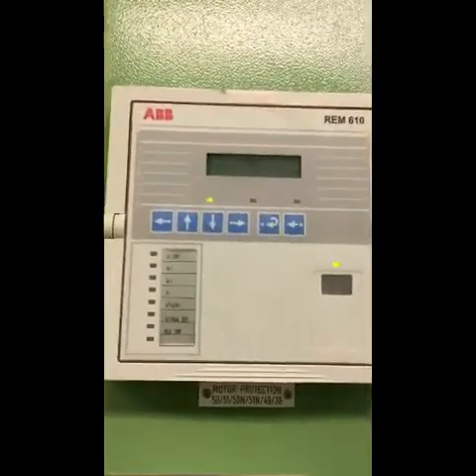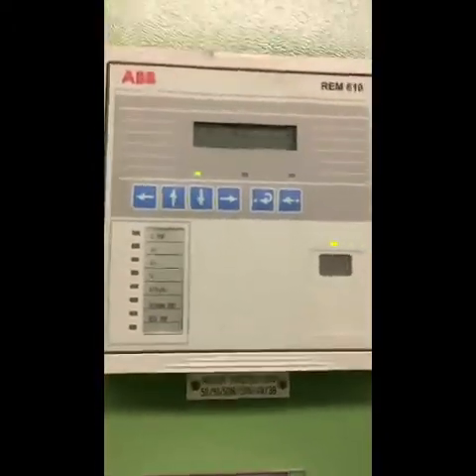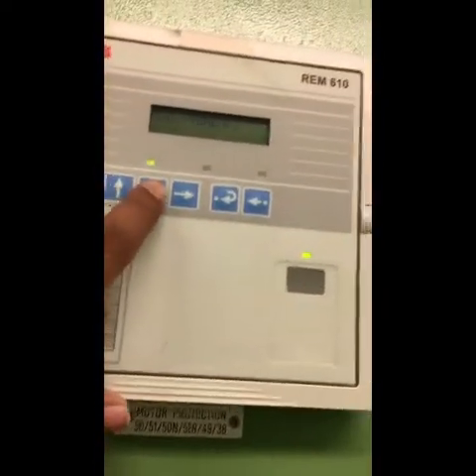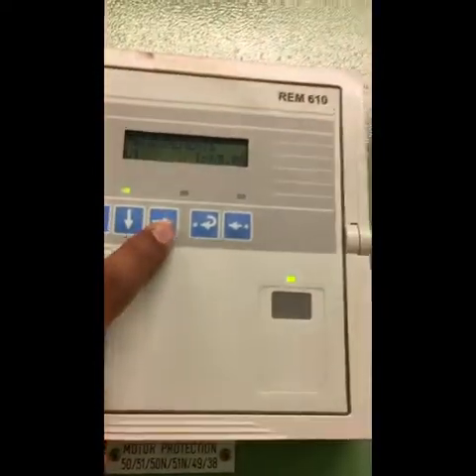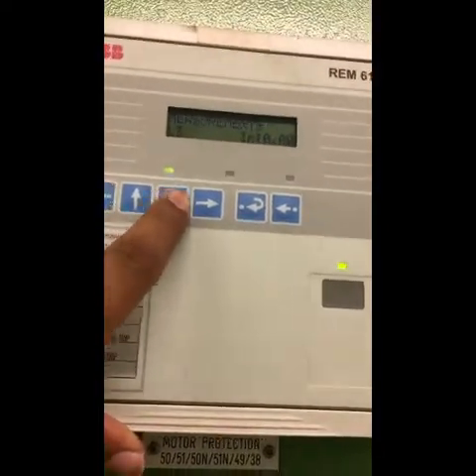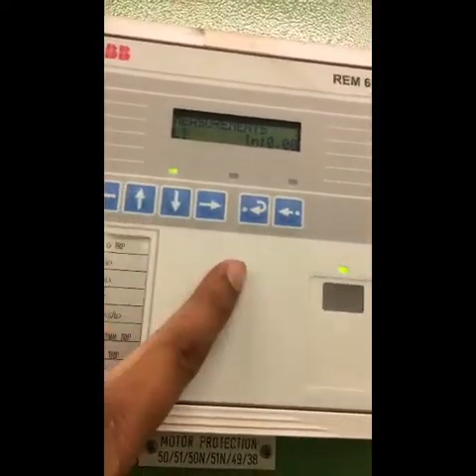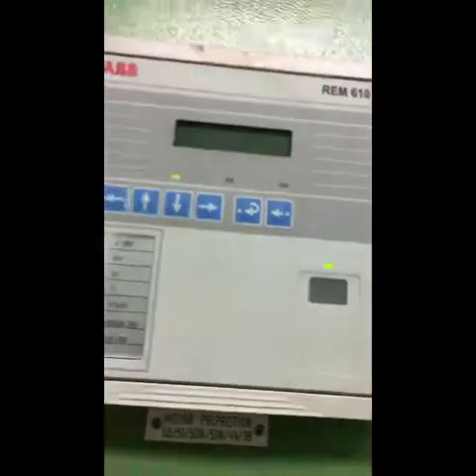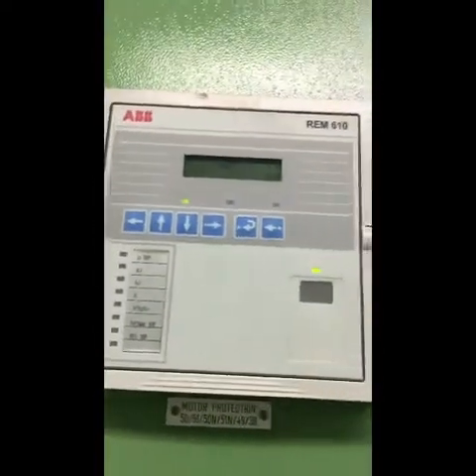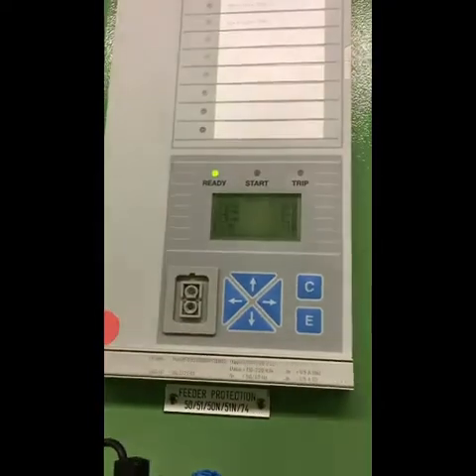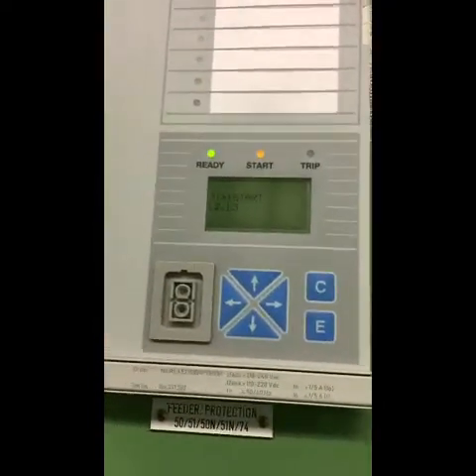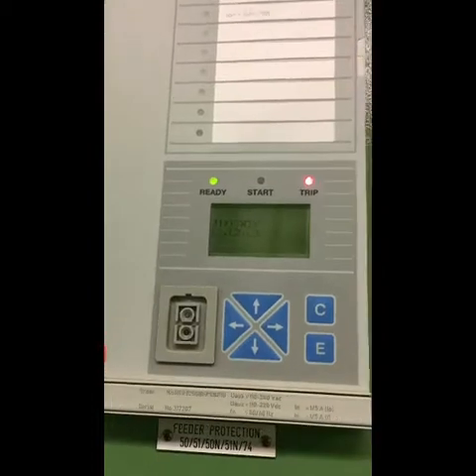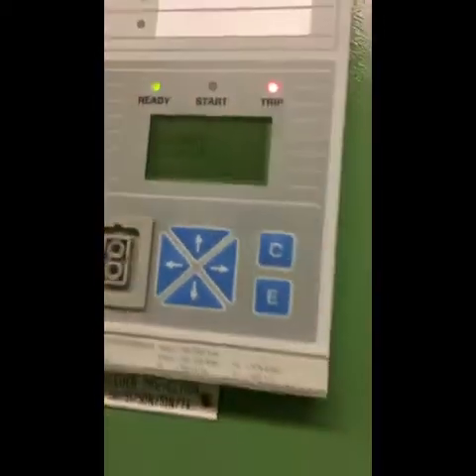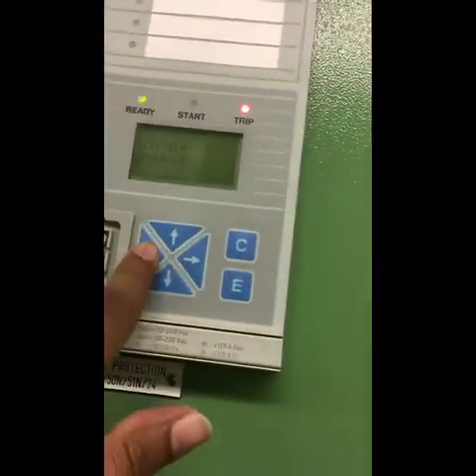And if you want to see the reading of the current from the relay, you can go to measurement, right click, line 1, line 2, line 3, and you can see the current that goes to the load. I just injected a fault current, and there is an alarm, so a trip happened, overcurrent greater, and we can see details of the tripping.